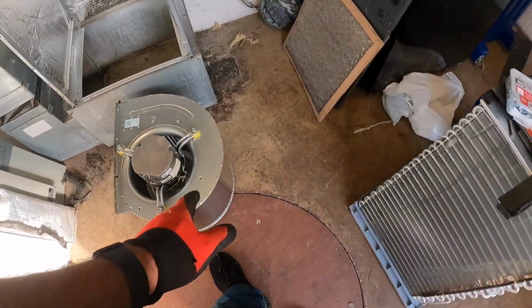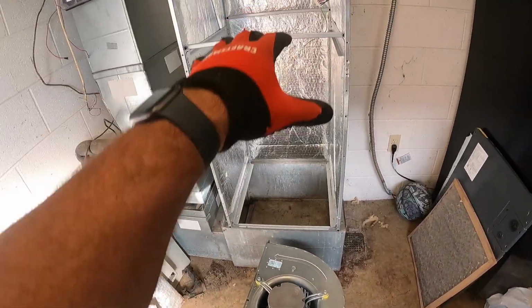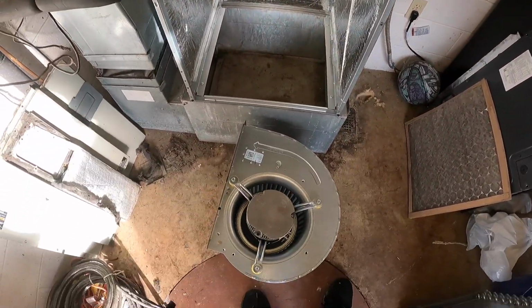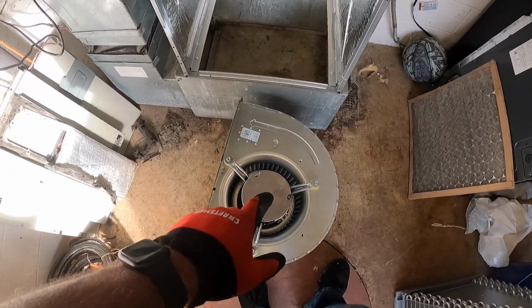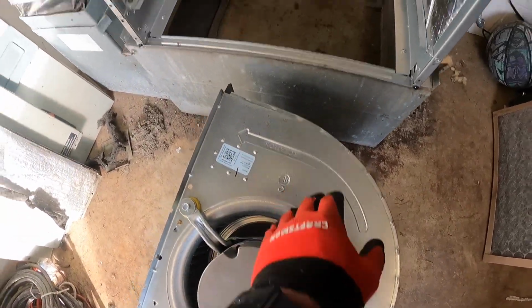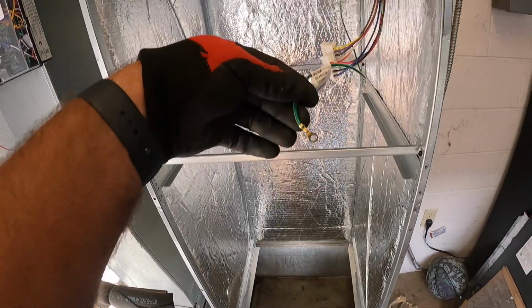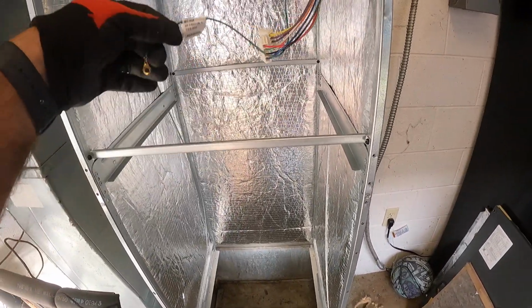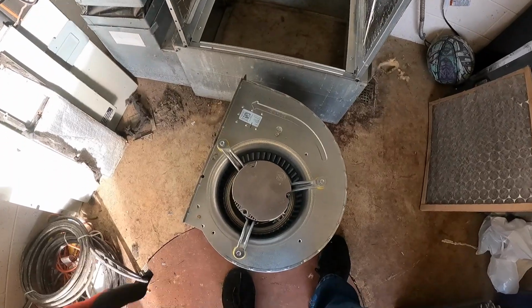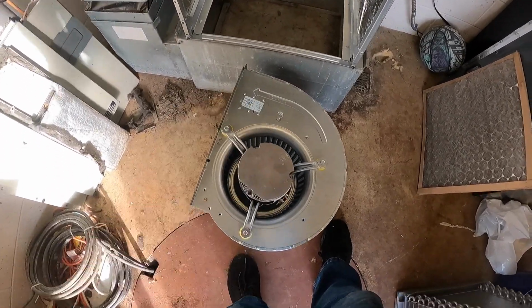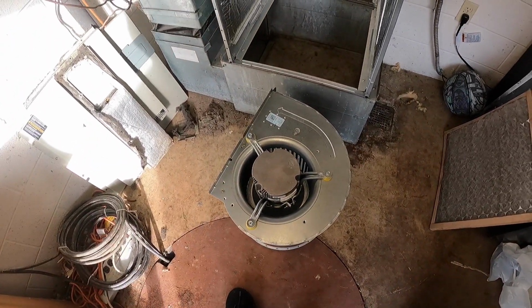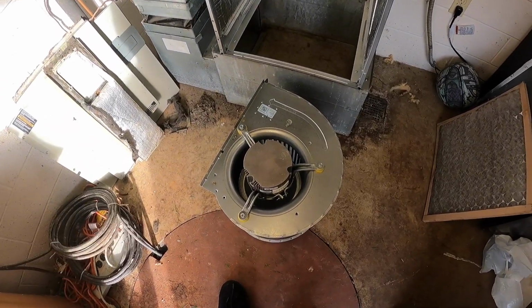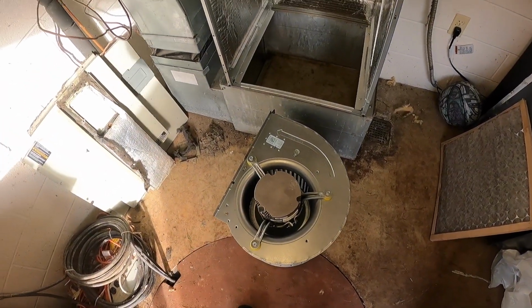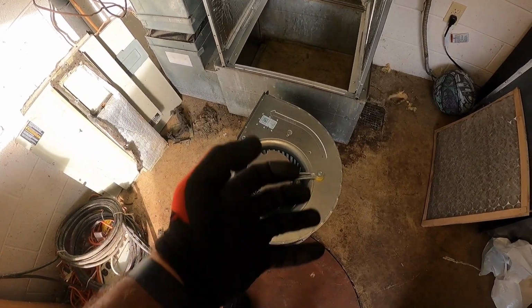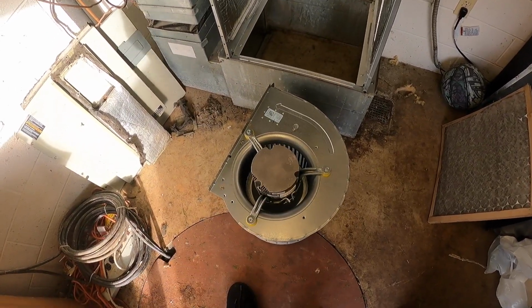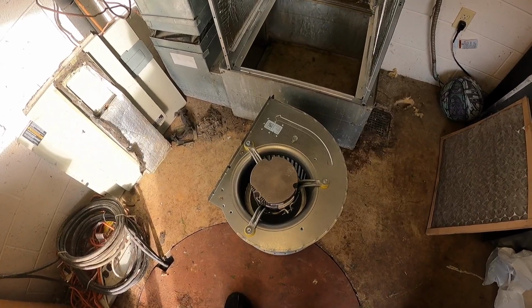I'm going to go ahead and throw this blower and coil back in there to give it some weight, so it'll be about as heavy as it's going to be. But I wanted to show you there's a ground screw and a ground wire connected into the harness on the back of the motor. They should have put it out front so you could take it loose before pulling the motor out, but they didn't — they put it in the back. So if you're in a tight spot and dragging the motor out, remember, once you get it out so far, you have to take that screw loose.